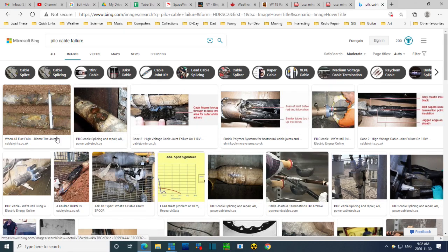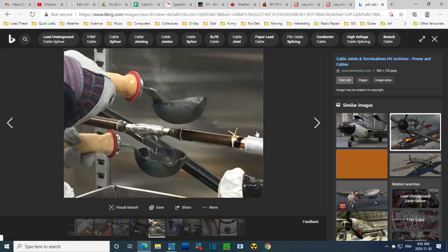Let me just show you some of the interesting things that are in here. Let's start with this one right here. I'll just click on it. So what's going on here is this is a cable. There's the conductor of another cable. This is paper insulation. Can you see the lap marks where it's been lapped on? And over here is some shielding. And this is lead, you can think of it like a lead pipe, although it's called a lead sheath. That makes the cable perfectly watertight, like any pipe would.